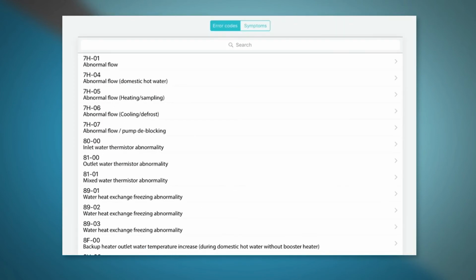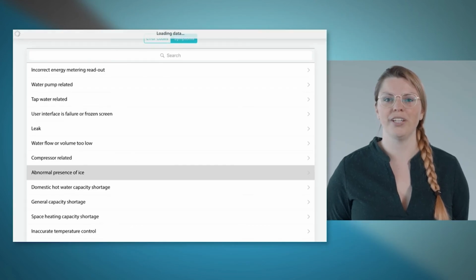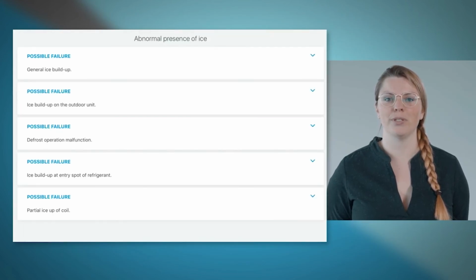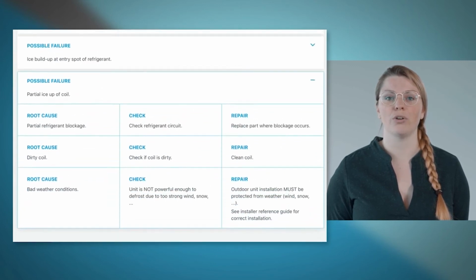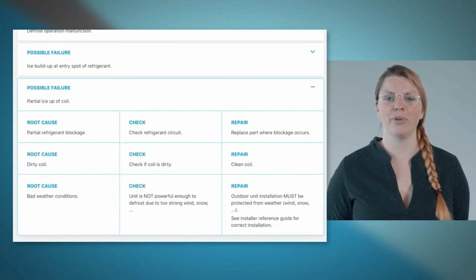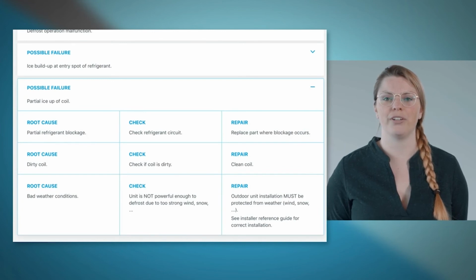We've now finished an example of how eDoctor guides you from error code to parts replacement. Let's go back to our troubleshooting and focus on symptoms now. In the symptom-based troubleshooting, we find a list of all known symptoms. Each symptom can have more than one possible failure, and a root cause, check, and repair instruction is given for each failure.